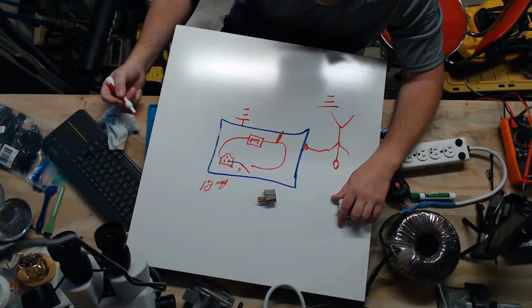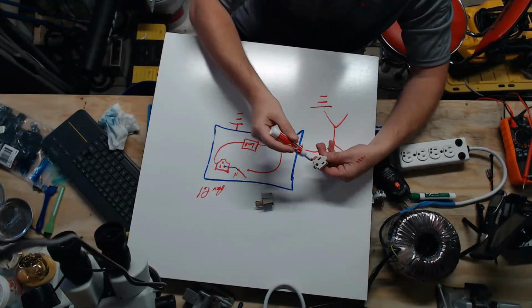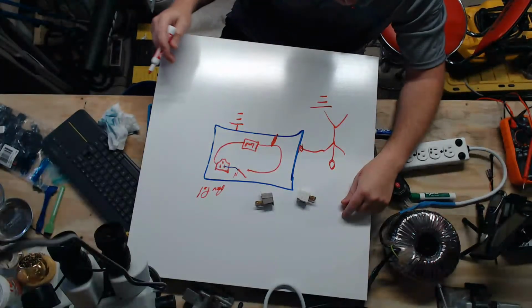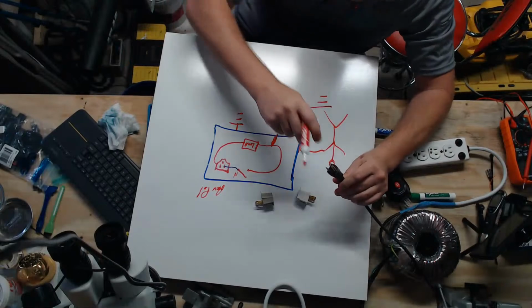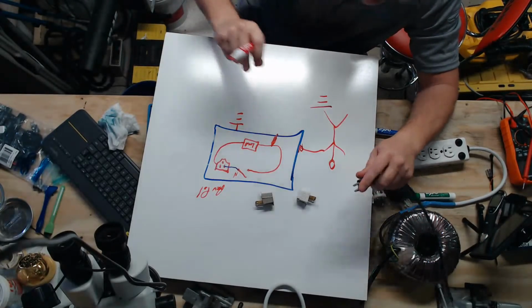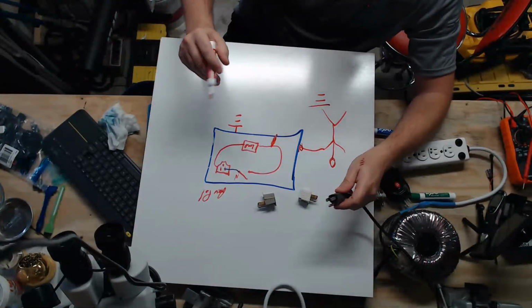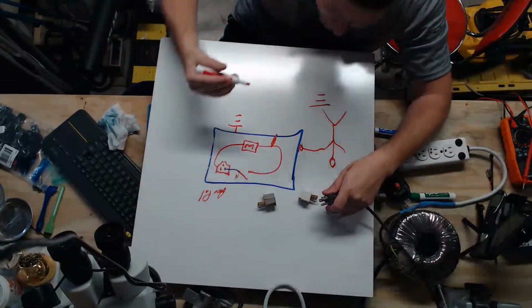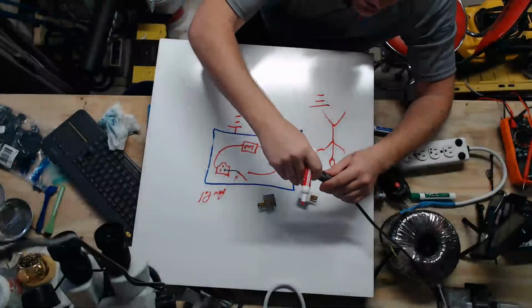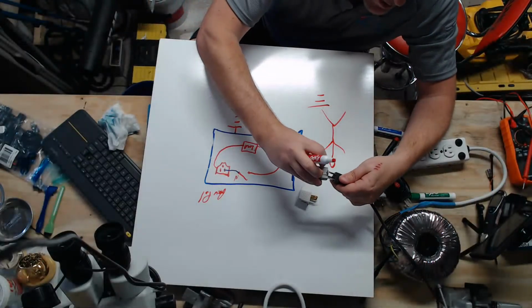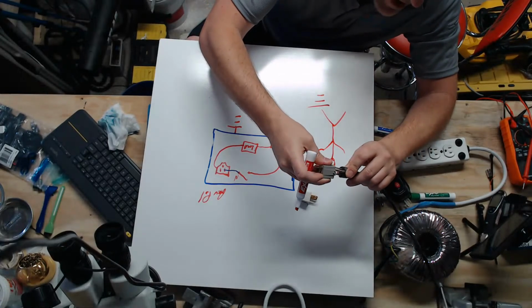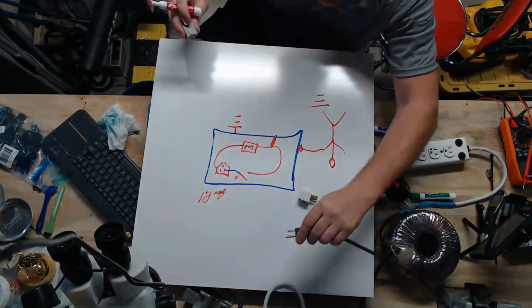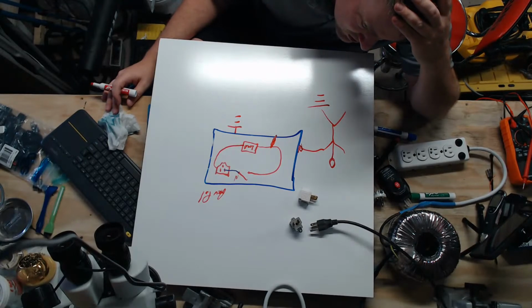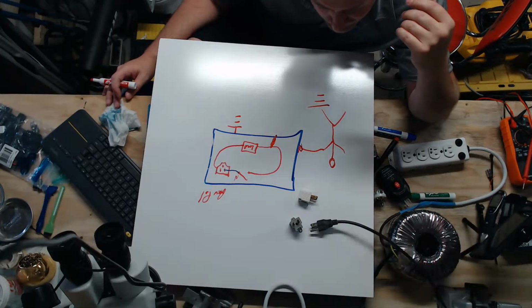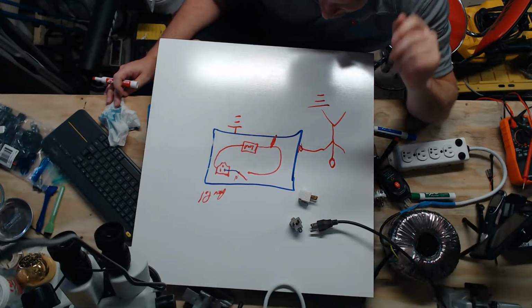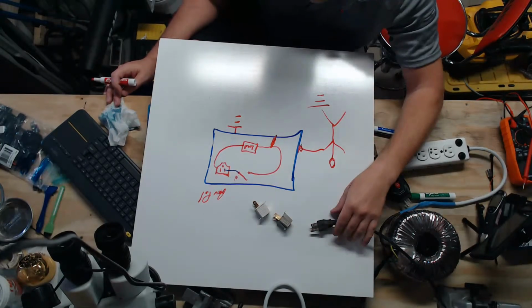All right. But it is not, because somebody got rid of this little ground right here using a cheater plug, or on a cord. See this cord right here? If this ground is broke off and somebody plugs it in upside down in a receptacle, you just negated all that electrical safety up until the point of the user. All right. I have seen this where you have a power strip and you have only so many outlets on the strip. And when people go to plug things in, you know, it doesn't quite fit. So sometimes people will snap the ground lug off and they'll put it in upside down. Guys, you just bypassed all your electrical safety code. All right. And you are gambling at that point. All right. This is a very, very serious problem. All right. Polarity does matter.